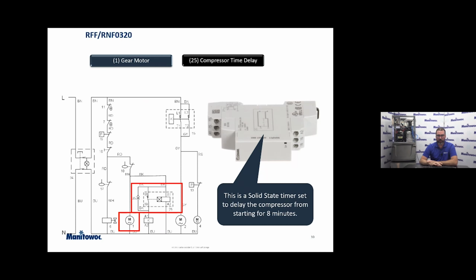So on this particular unit, we're using a solid state timing relay. What this is doing is just giving that system time to fill up with water and get everything turning before we just automatically go and start up that compressor. We want to make sure that we've got the system operating properly. It doesn't pay to start a compressor on a system that's malfunctioning. So it just gives us 8 minutes to get that system up and running and kind of normalized, per se. So of course, for the first 8 minutes of operation on a 320, you're not going to see that compressor motor engage. It's going to be timing, waiting for that delay to end, in this scenario 8 minutes.